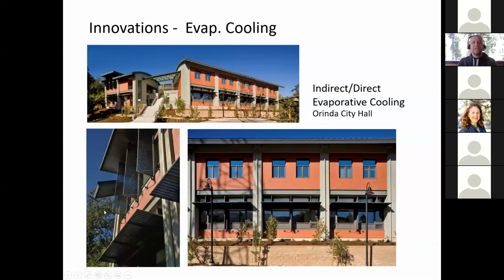And then on this other facade facing a little bit more westerly, again deep overhang plus vertical fins to help with the shading. So a lot of effort to bring down the loads, make the cooling loads low, so that you can use evaporative cooling for the project.